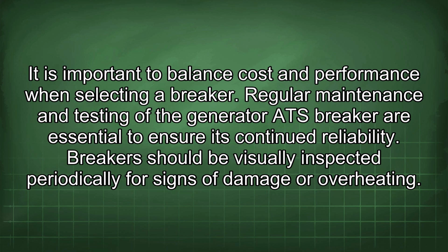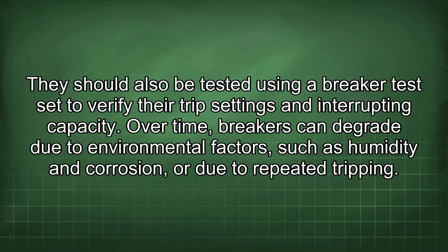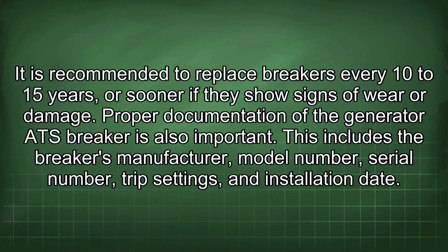Regular maintenance and testing of the generator ATS breaker are essential to ensure its continued reliability. Breakers should be visually inspected periodically for signs of damage or overheating. They should also be tested using a breaker test set to verify their trip settings and interrupting capacity. Over time, breakers can degrade due to environmental factors such as humidity and corrosion, or due to repeated tripping. It is recommended to replace breakers every 10 to 15 years, or sooner if they show signs of wear or damage. Proper documentation of the generator ATS breaker is also important.